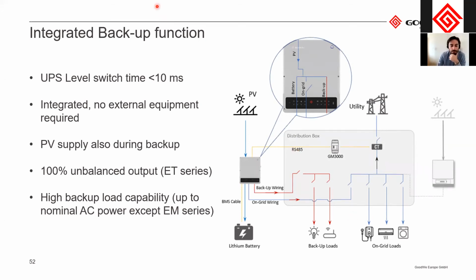This is one of the most liked features of our hybrid system: the integrated backup function. This means that when the grid fails, you still have some loads that are powered from the PV and the battery. Here you see a short diagram. Let's say you already have a PV connected system. Here's the grid, and here are your loads, your household. Then you can install an additional PV system with our hybrid inverter or battery inverter. This is actually not necessary, but you can install this directly as well. Then you have your household loads here, and here are your backup loads, the battery and the PV system. In case the grid fails, all these loads will be disconnected, but the loads connected to the backup will keep being supplied.